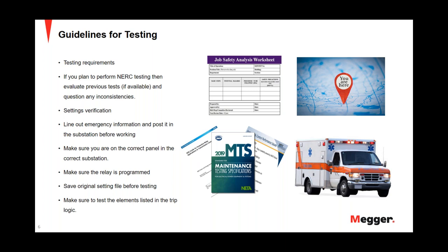Setting verification is very important. A couple of years back I came across a generator relay that didn't have any settings in it — it had been running for a few years with no settings. When I went to the relay to perform maintenance testing, nothing was enabled, there was no logic, it was like it was never programmed. What had happened was the previous test group pulled the settings out and saved them but never compared what they pulled out with what was actually in the relay. So the equipment had been running with no settings.